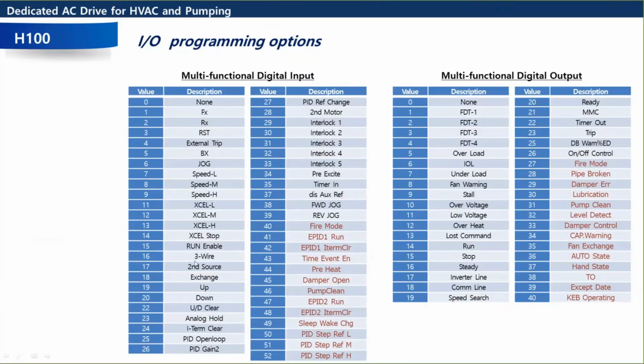3-wire for push buttons. Second source to switch between analog inputs or communications or whatever. We have up-down control, which is called MOP sometimes. Analog input holds. Got a bunch of PID stuff here.